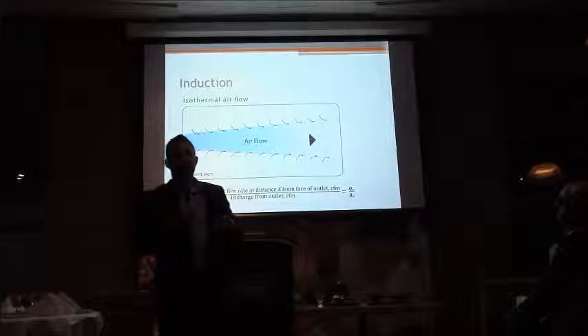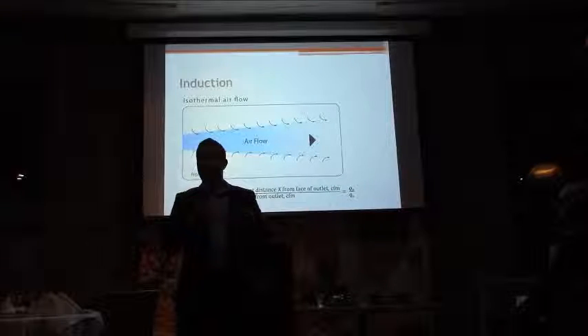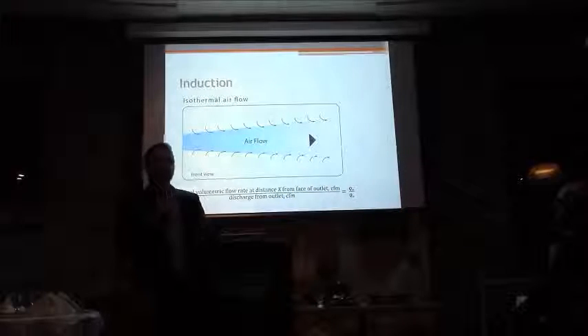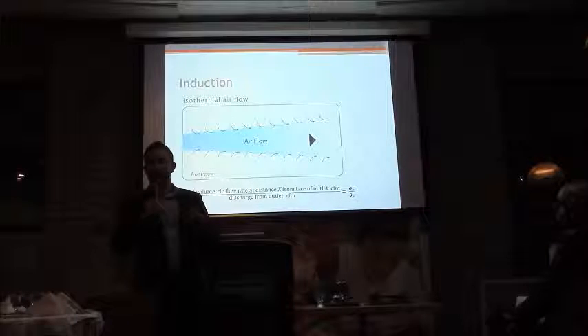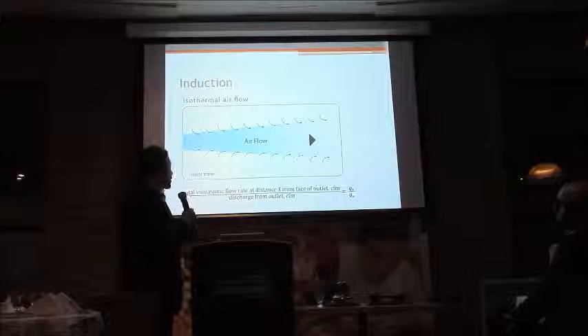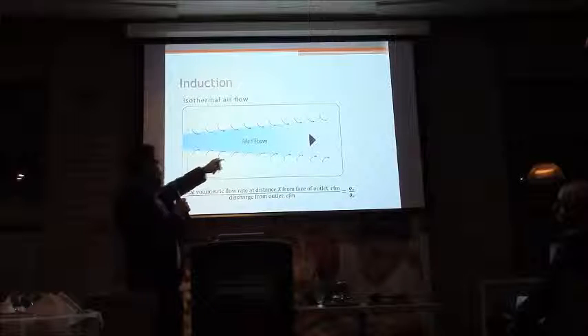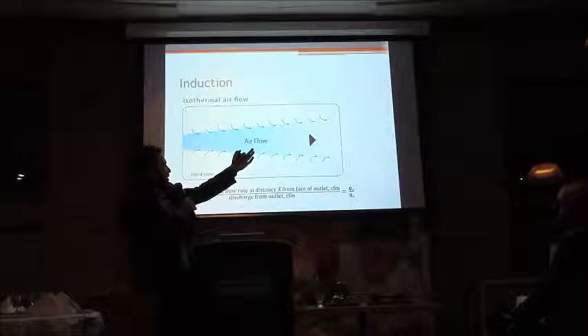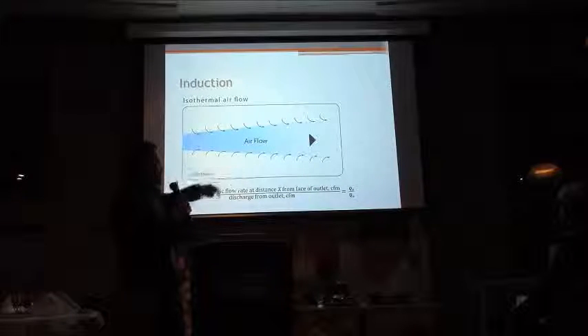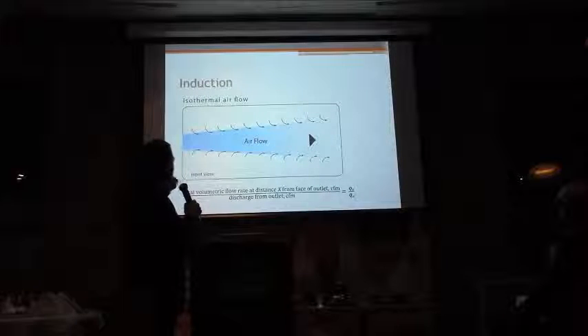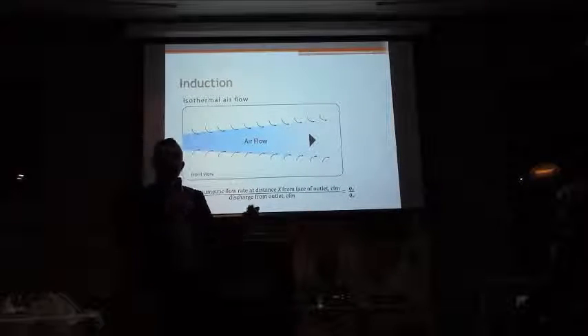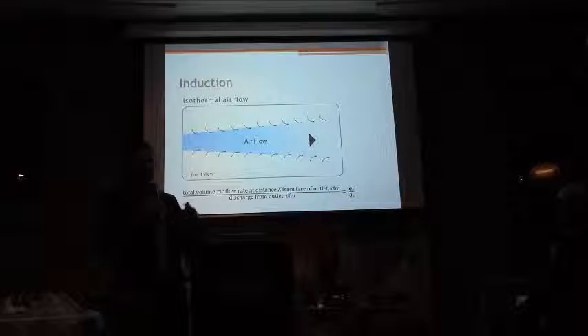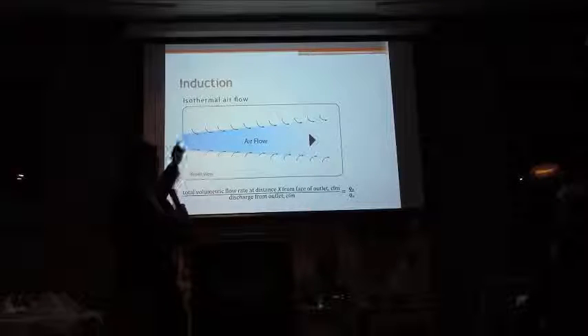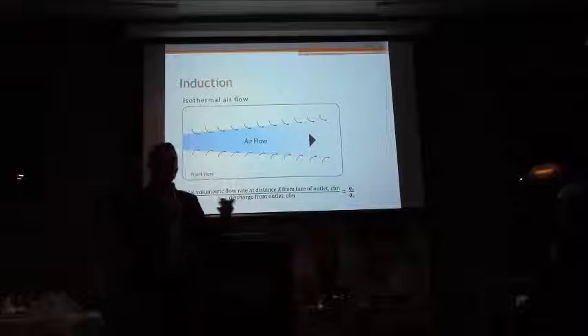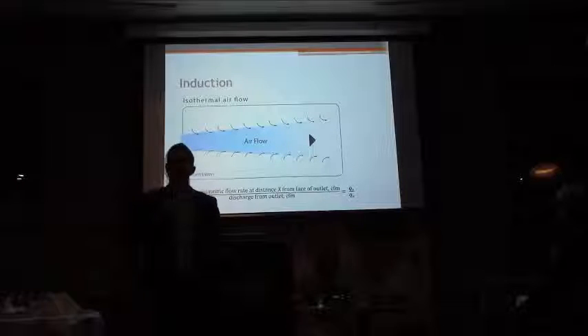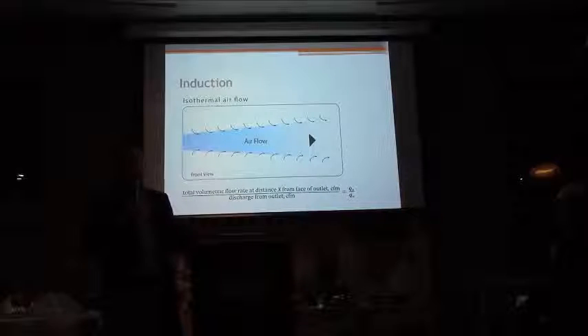If I'm going to talk about high induction diffusers, the best place to start is to explain what induction is and what differentiates a high induction diffuser from a standard diffuser. So what is high induction? If we look at isothermal airflow, this is isothermal airflow. The reason it's isothermal is that it's straight. If it was heating, you would see it move a bit up, and cooling, a bit down. The black arrows right there are room air being induced by your primary air. The primary air is the air coming out of your diffuser, and the secondary air is all the room air being induced by your primary air. So it's kind of an entrainment ratio.